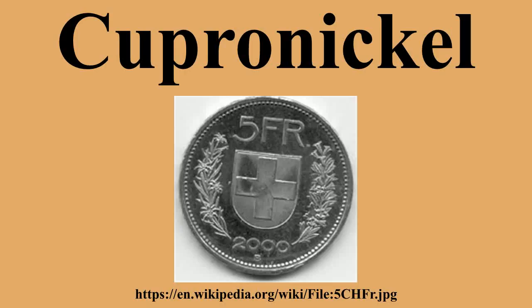Brazing requires appropriate silver-based brazing alloys. However, great care must be taken to ensure that there are no stresses in the cupronickel being silver brazed, since any stress can cause intergranular penetration of the brazing material and severe stress cracking. Thus, full annealing of any potential mechanical stress is necessary.